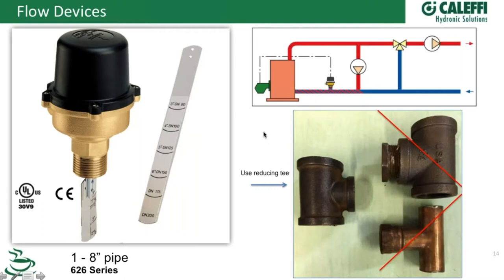Where this flow switch is typically used — I see it most commonly on domestic water boilers, typically a copper tube boiler. The flow switch makes sure that if there's no flow going through the boiler, it cuts off the burner so you don't just boil the water in there. It has to have a certain amount of flow going through that boiler to pull the heat out as fast as the burner is making it, so you don't have an overheating condition, which could lead to a trip on the relief valve. Other applications: you'll sometimes see them on heat pumps where we're going to trip off the heat pump on a pump and dump — you want to make sure there's flow going through so you don't overheat the loop and trip out on the compressor.